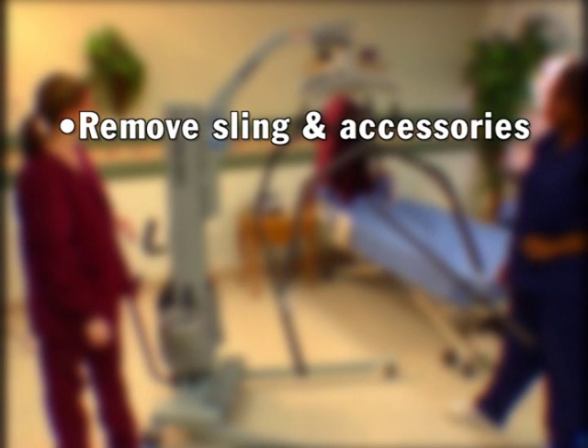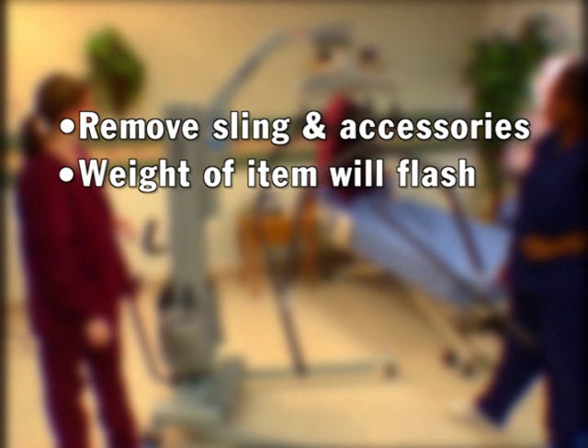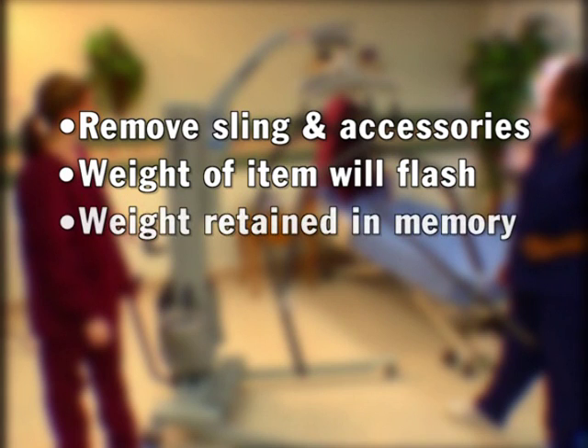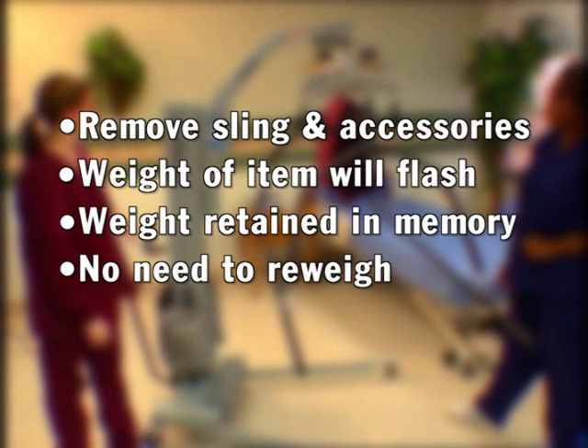Remove the sling and accessories from the hanger bar and view the scale readout. The weight of the items will flash and will be subtracted once the resident is weighed. This weight reading will be retained in memory, even if the scale shuts down on its own. Thus, if weighing more than one resident, you do not have to re-weigh that accessory unless you choose a different size or type.